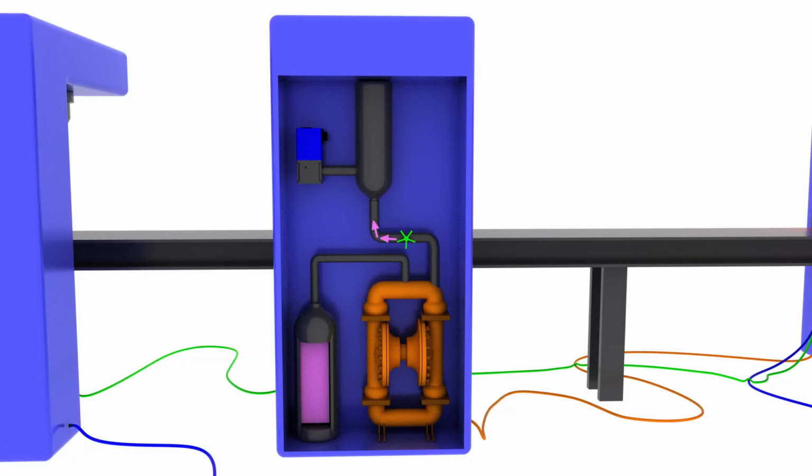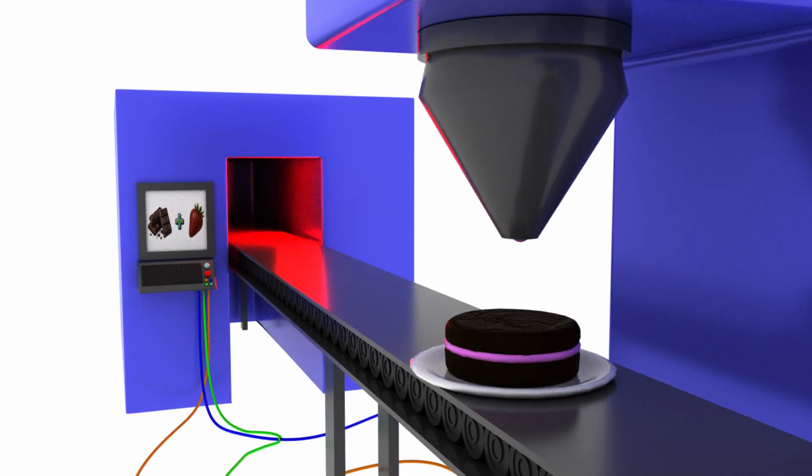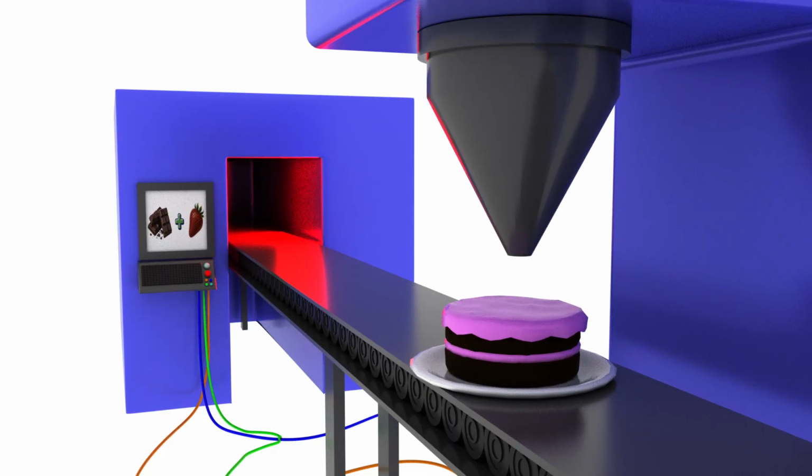The required airflow depends on the volume of the tank and the dispensing speed. With flow capacity up to 30 standard cubic feet per minute, the QB3 can meet the demands of this process while controlling pressure with an accuracy of plus or minus 0.25% of full-scale calibration.